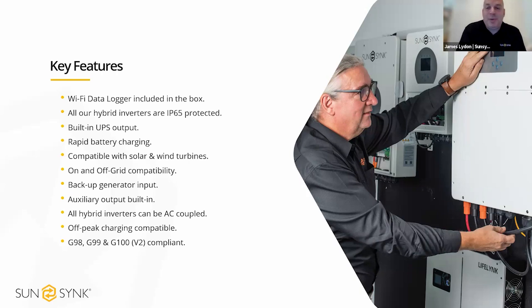Okay, off-peak charging compatible, so very standard. We're fully compatible with Octopus, so we've got the full Octopus API, so we can control the battery charge and discharge rates dependent on the tariff. We're compatible with the Agile and the Flux. If someone's on a standard off-peak tariff, let's say midnight till 6 in the morning, that can be programmed on the inverter, and that will take effect every day.